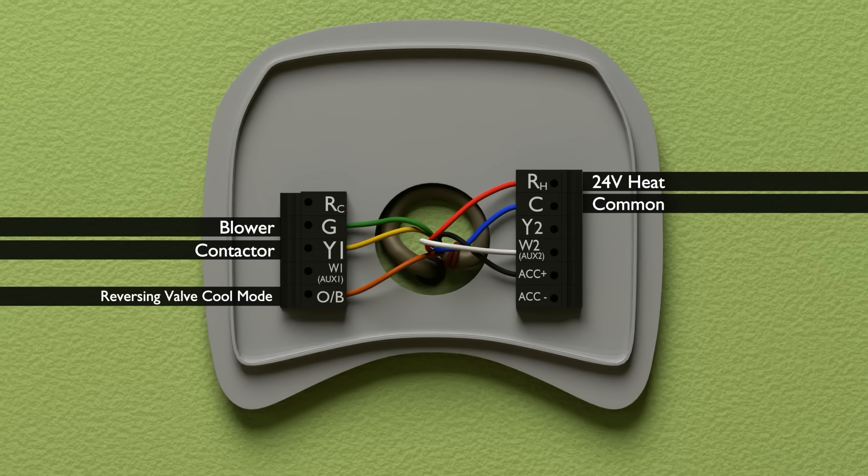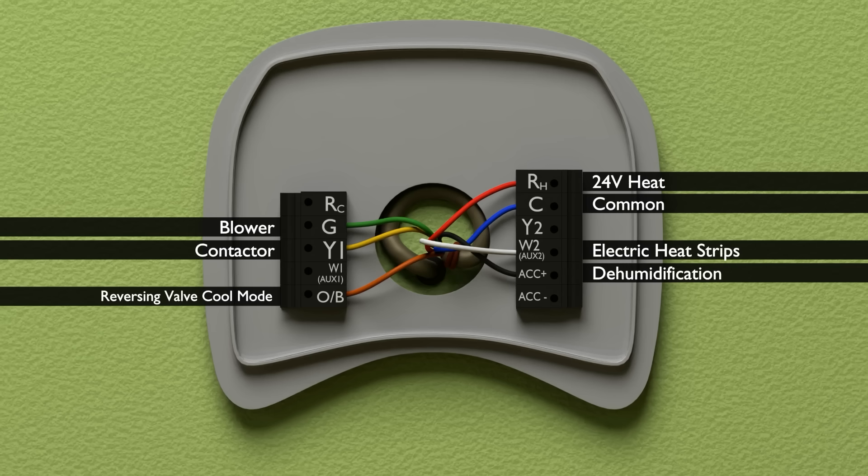C is for common, which is the path back to our transformer. W2 or aux, auxiliary heat, is our electric heat strips. And in this case, we're using the ACC plus setup for dehumidification. This is set up within the menu of the thermostat.